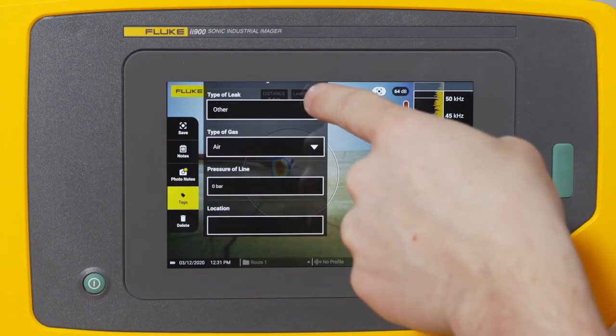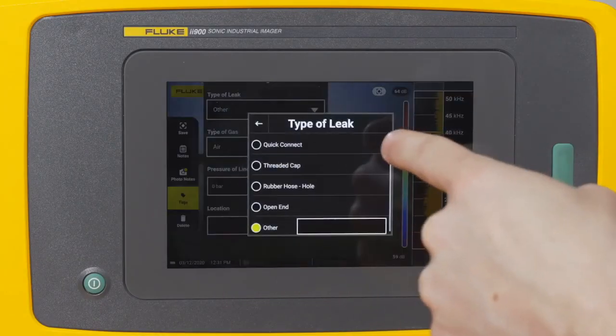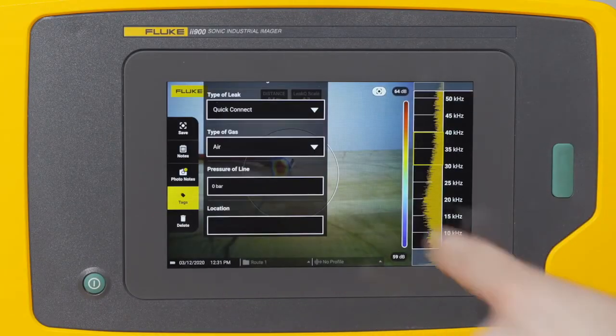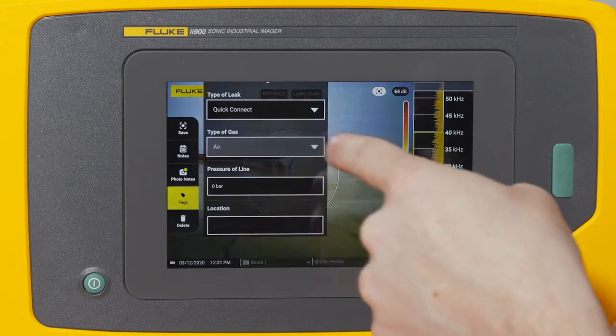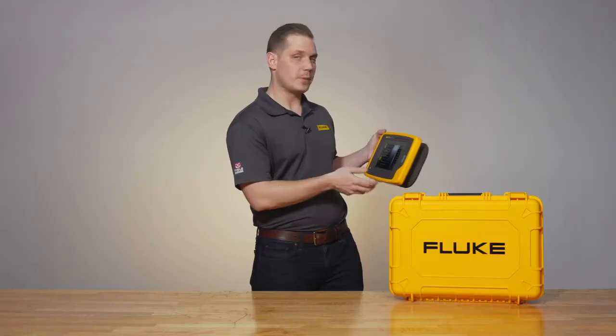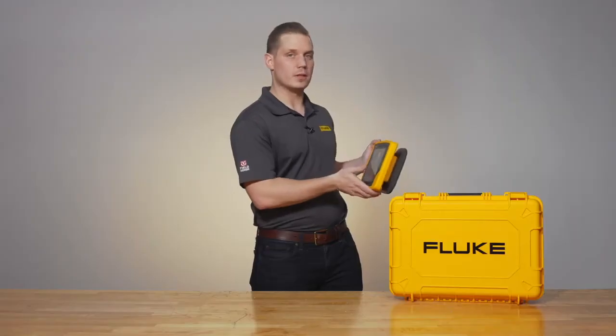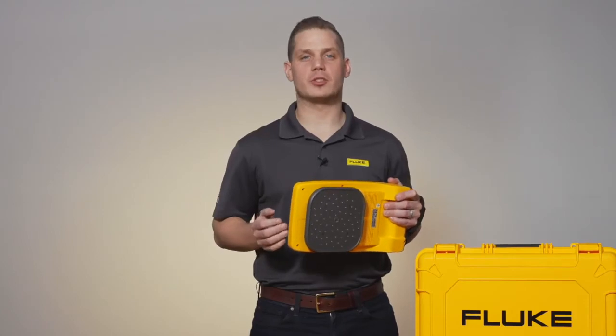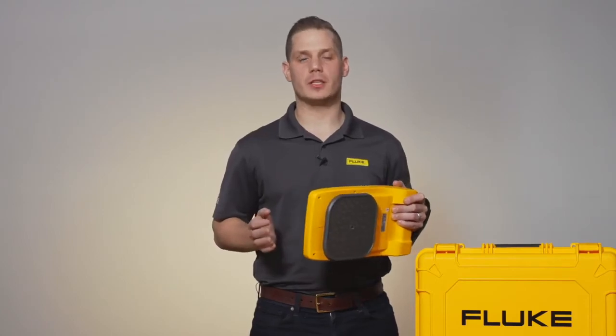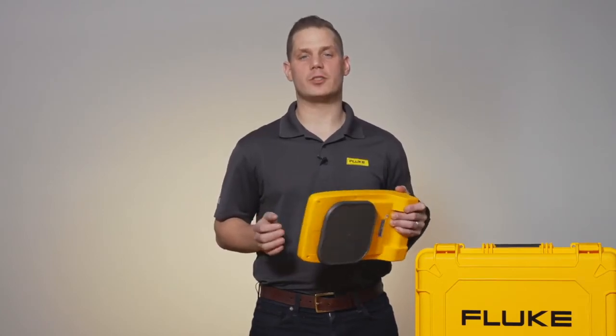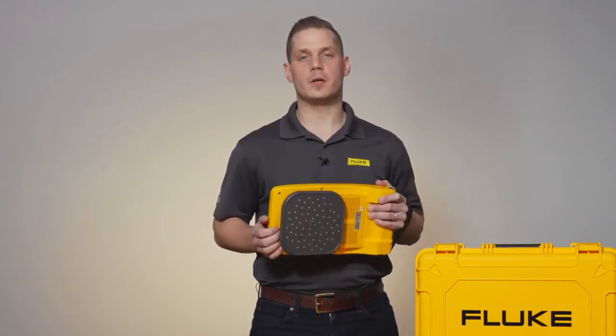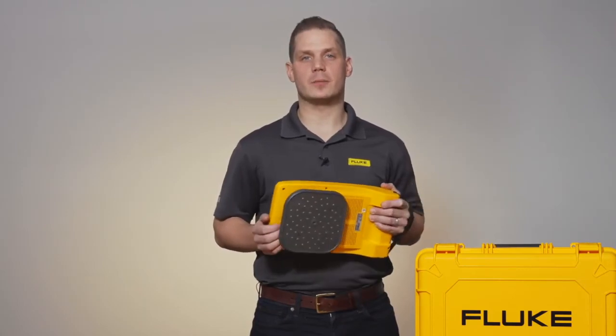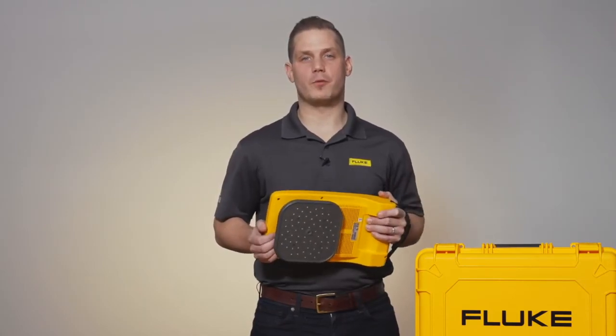Tags will allow you to add other information to your image like the type of leak, the type of gas, the pressure of the line, or the location of the leak. The ii900 captures all of this information in a single file called an is2 file, but if you prefer, it also captures images in JPEG format.